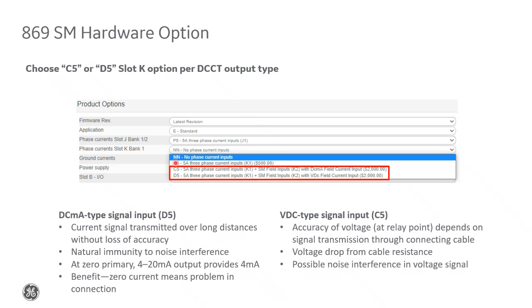This does not have a synchronous motor option. Or you can choose these C5 or D5 options, which include the synchronous motor option. So these two options specifically indicate that you want the synchronous motor option. There's nowhere else in the order code where you specify it. With them, you get this second CT bank for differential, and you'll also get another set of inputs for all the synchronous motor inputs that we talked about.